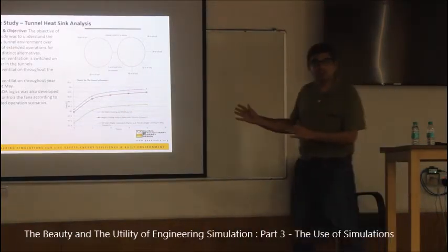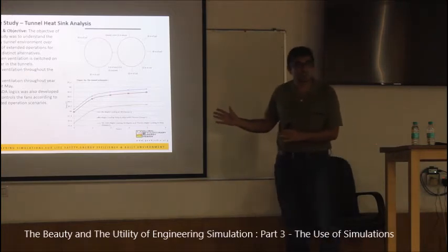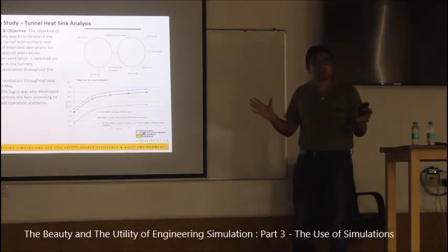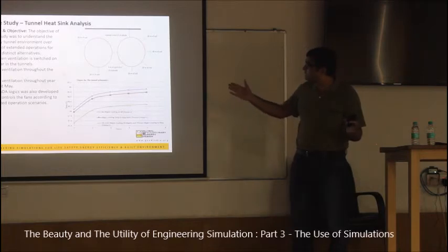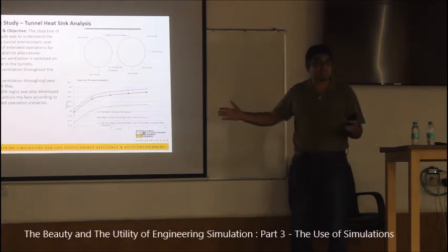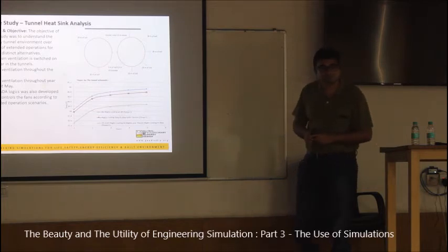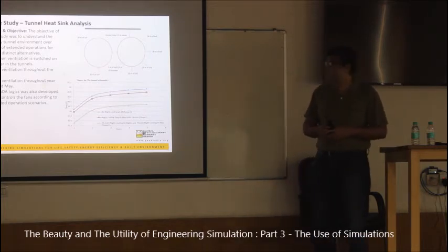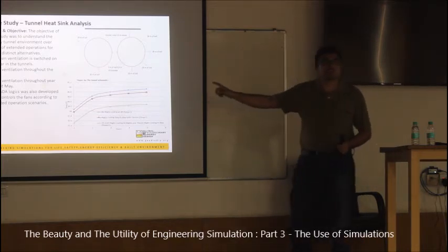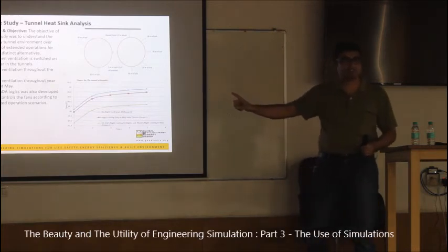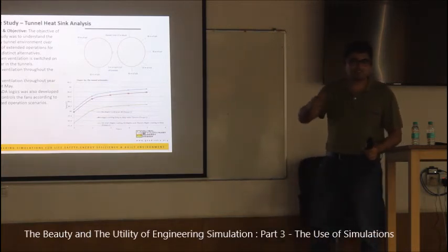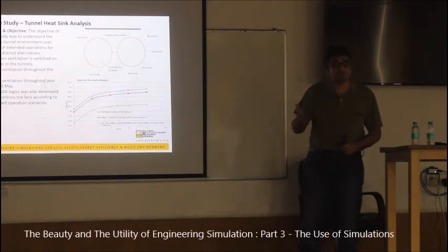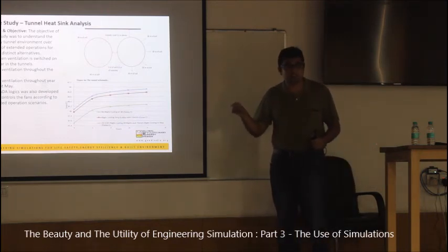So here you have a real use of simulation to understand how the systems are behaving. And mind you, this is highly transient: the heat transfer phenomena are coming up and going within 2.5 minutes. This temperature is the peak temperature of a year. So what we are interested in is the peak temperature. If we limit it to 50 degrees centigrade, we are done.